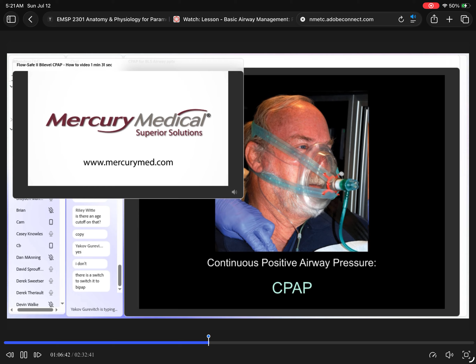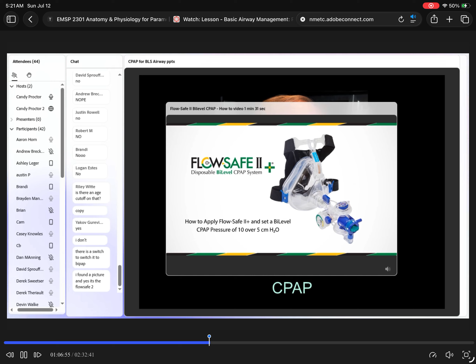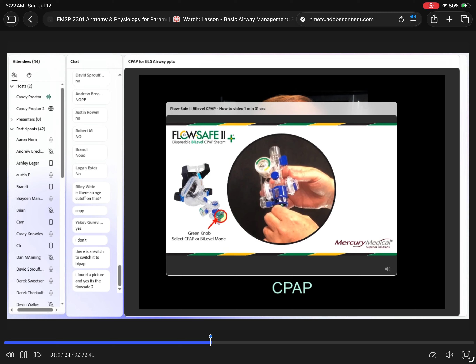So here we go. FlowSafe 2 bi-level CPAP. Here are important instructions for applying and setting a bi-level CPAP pressure of 10 over 5 centimeters of water pressure on the FlowSafe 2 Plus. All right, so 10 over 5. When you talk about BiPAP, there's a pressure setting for inspiration, which is the higher pressure, and a lower setting during the exhalatory phase, which would be the lower number. So this is set for 10 during the inspiratory phase and 5 during the exhalatory phase.